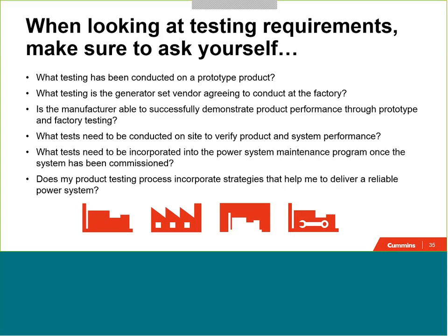Above and beyond prototype testing and factory testing, ensure that, one, you're aware of the site testing requirements, especially if there are site testing requirements specified by a local authority, and ensure those are clearly communicated to all generator set vendors or all product vendors so that they can ensure that that product, when it arrives on site, will meet those testing guidelines.